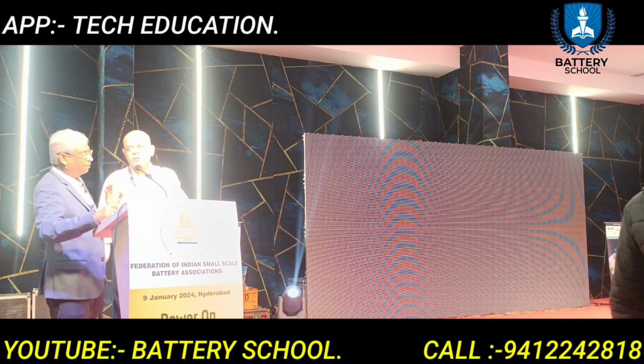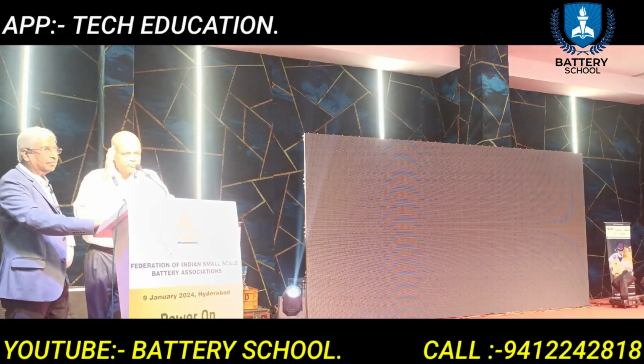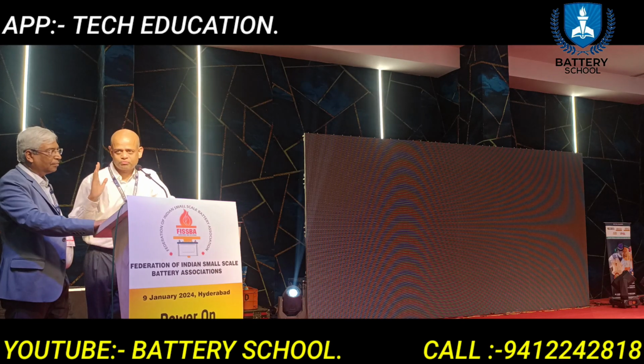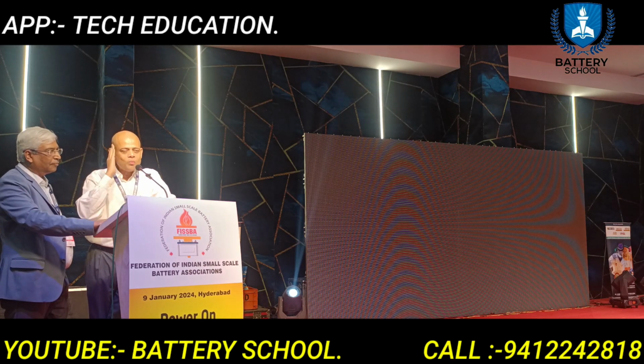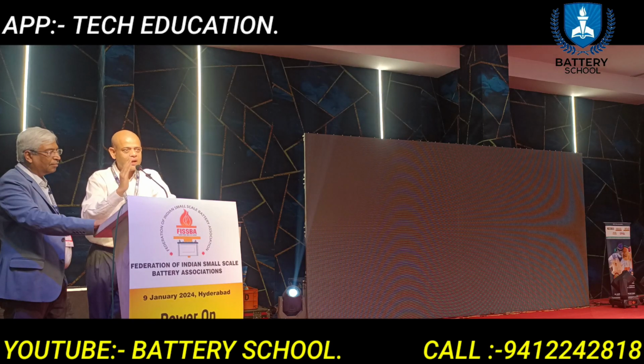No. What I'm talking about is, let's say a set of 12 batteries. If you take a 12 volt monoblock, I have 12 multiplied by 6, so 72 cells. Now the question is, how have these 72 cells been manufactured? Both positive plate and negative plate, what is the variation available in that? As a group, I need to consider that. So that's where my plate weights are important.